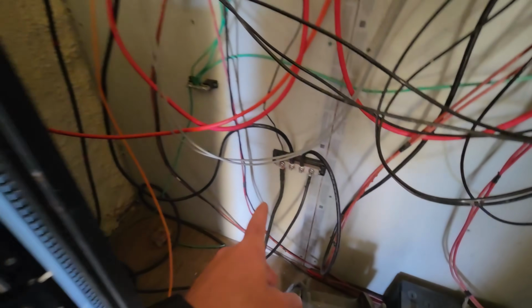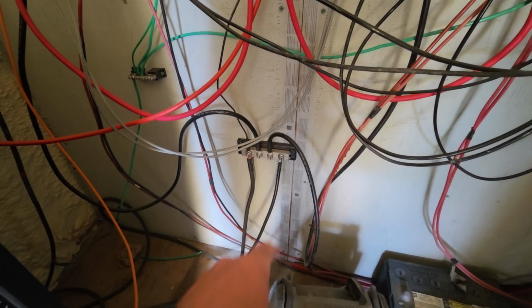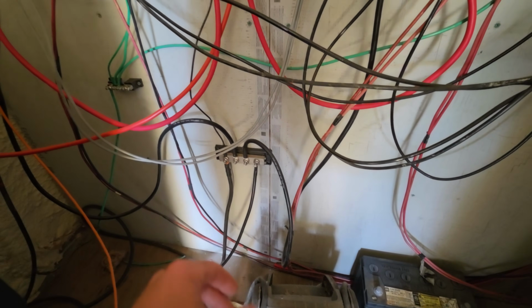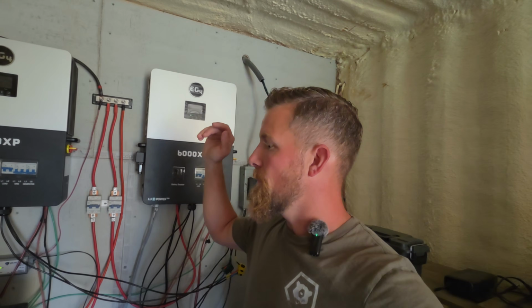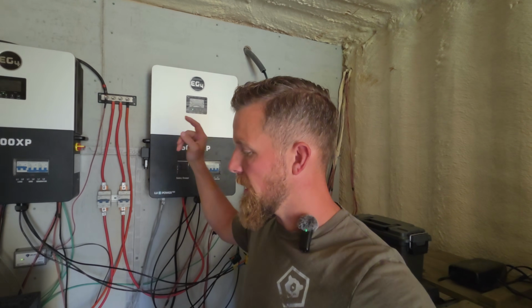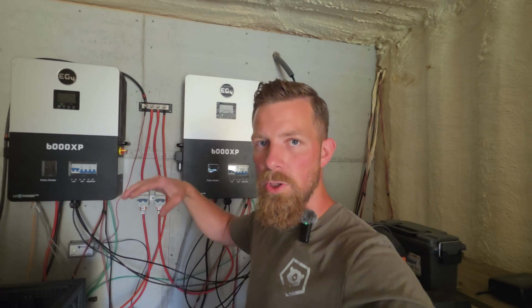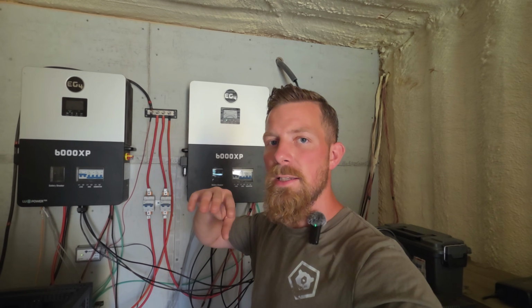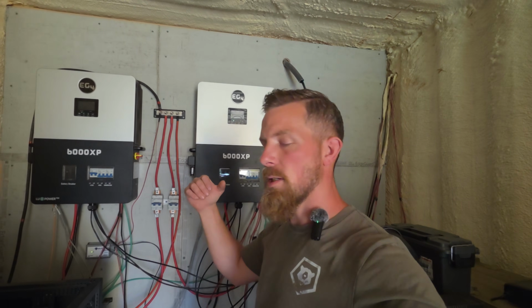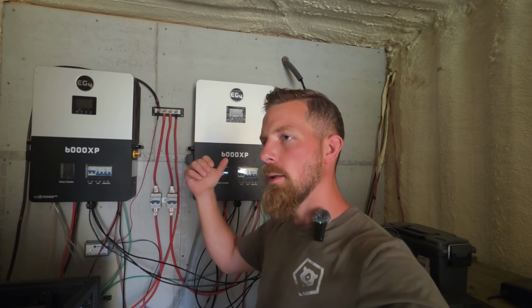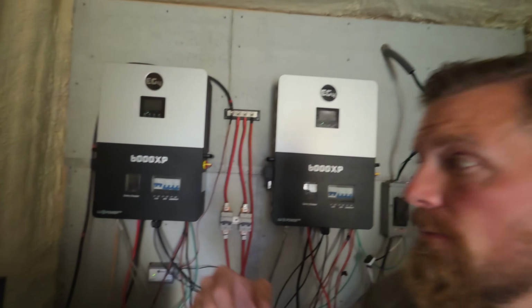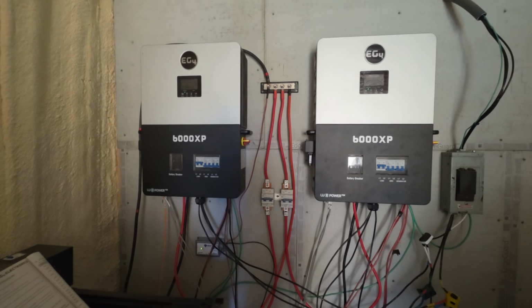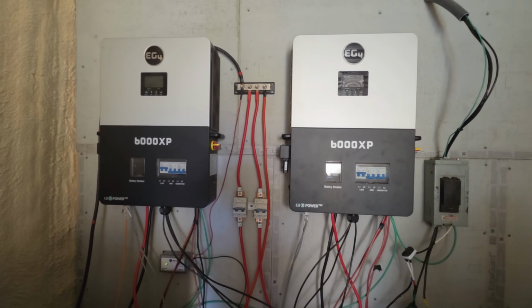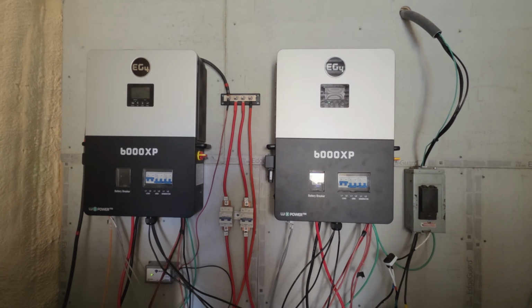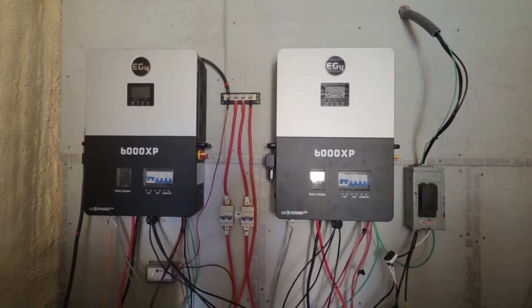As you can see, my bus bars are a little small, meaning they're completely full. So I've got larger bus bars to put on here, and we're going to tie this into the main system. We'll leave it communicating with the EG4 server rack batteries, and since this has its own BMS built in, we're going to tie it into the same bus bar and expand the system. This should allow me to flip the entire homestead over to solar power and run it like that. This is a huge step in the right direction.